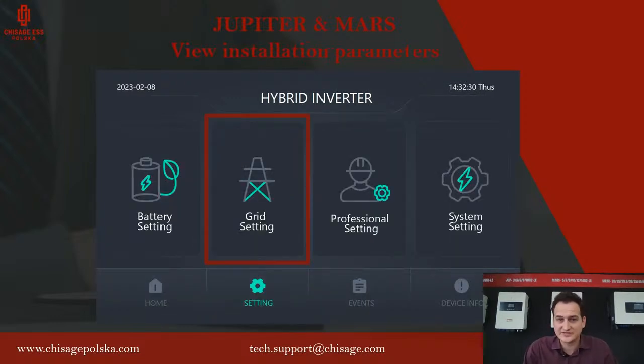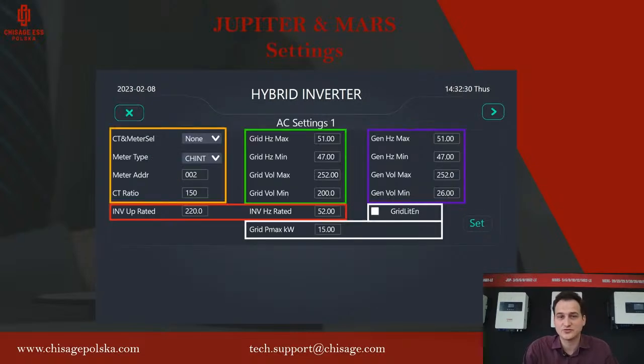Then we have the grid settings. So the battery settings first, then we go to grid settings. Here on the left, we have to set up the CT or meter options. So we pick CT and CT ratio. If we have a meter, we have to pick the meter type and the meter address. For meter address, you have to put 005, because that's the meter address our inverter works with. So 005 for meter address, type Chint or Eastron, and CT or meter, so then we pick meter.